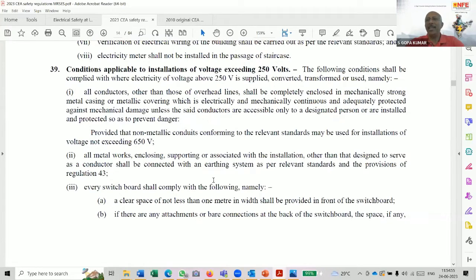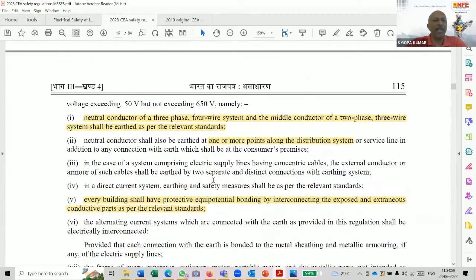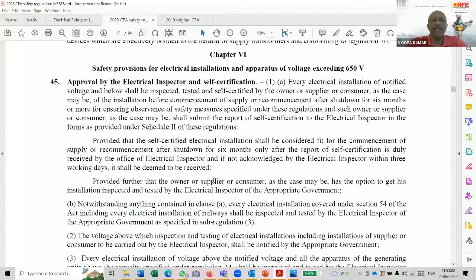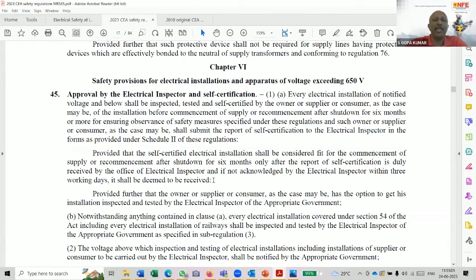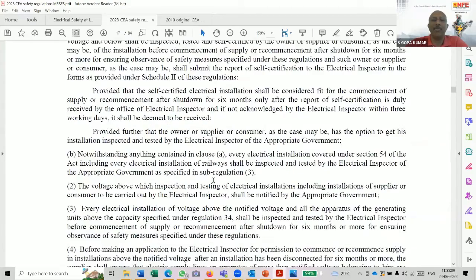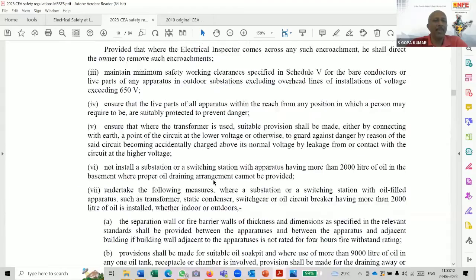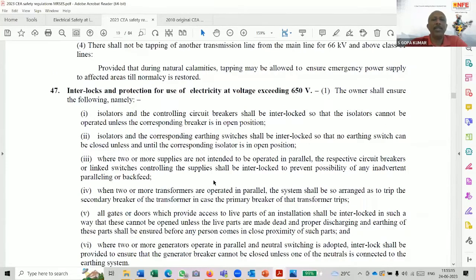So coming back to the question regarding regulation number 47, the question is to Appavu sir. Sir, in chapter 6, safety provisions for electrical installation and apparatus of voltage exceeding 650 volt, regulation number 47, which is talking about the interlocks and protection of use of electricity at voltage exceeding 650 volt. Here the provisions for avoiding neutral circulating current have been made. This is also applicable for low voltage, but this regulation has come under the heading exceeding 650 volt. What is your opinion on this?